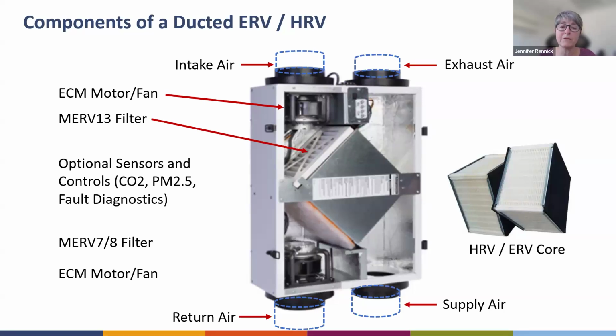That MERV 13 is part of the Title 24 requirements, and that's a filter that can be easily changed and replaced. And then you're going to have another ECM motor for pulling the return air in. And it's also going to have a small MERV 7/8 filter on it just to protect the heating, the HRV or the ERV core. And then that core is a cube for the residential size. It's about 5 inches by 5 inches or so.